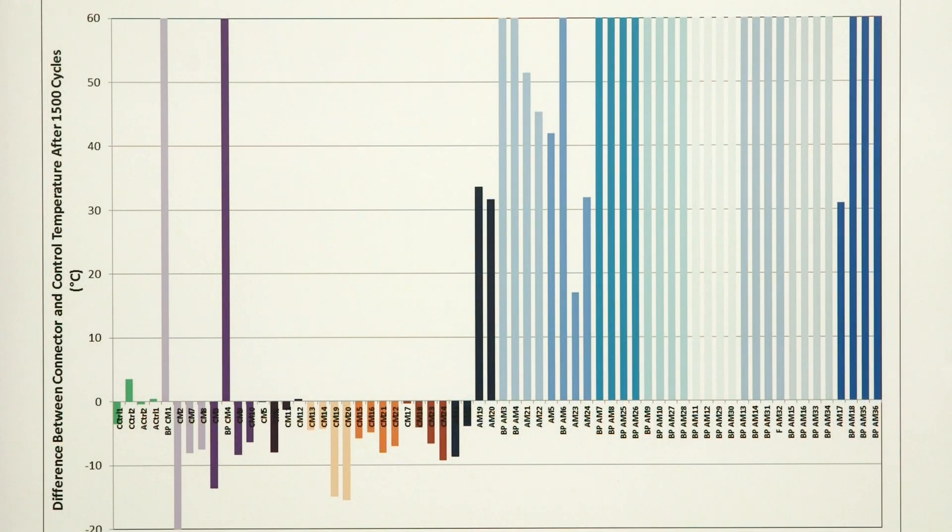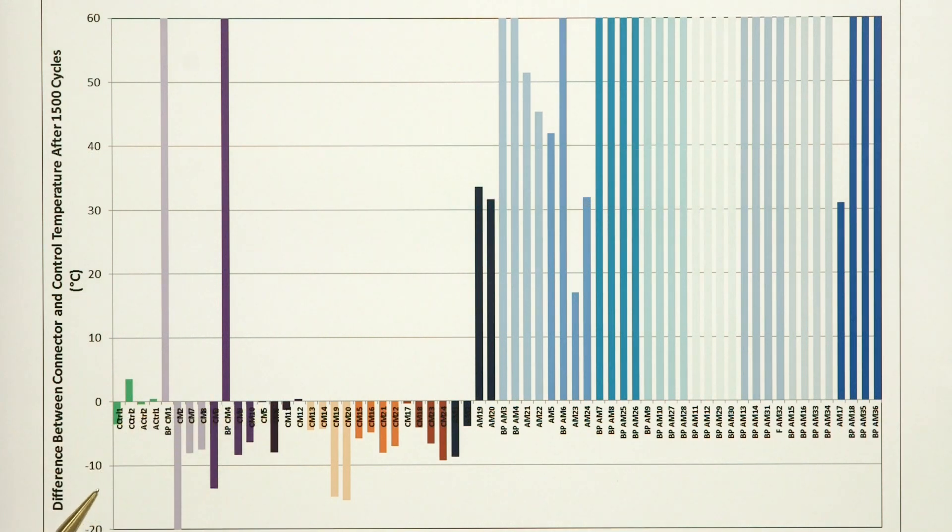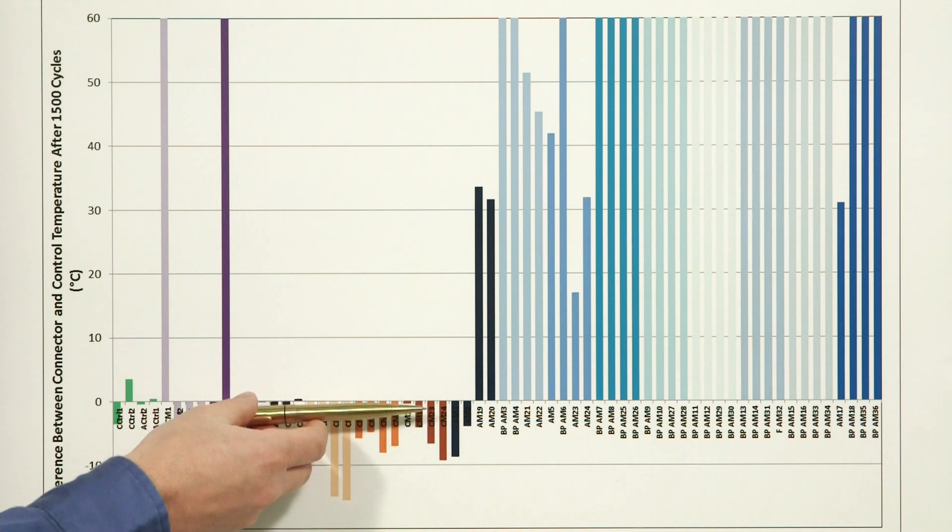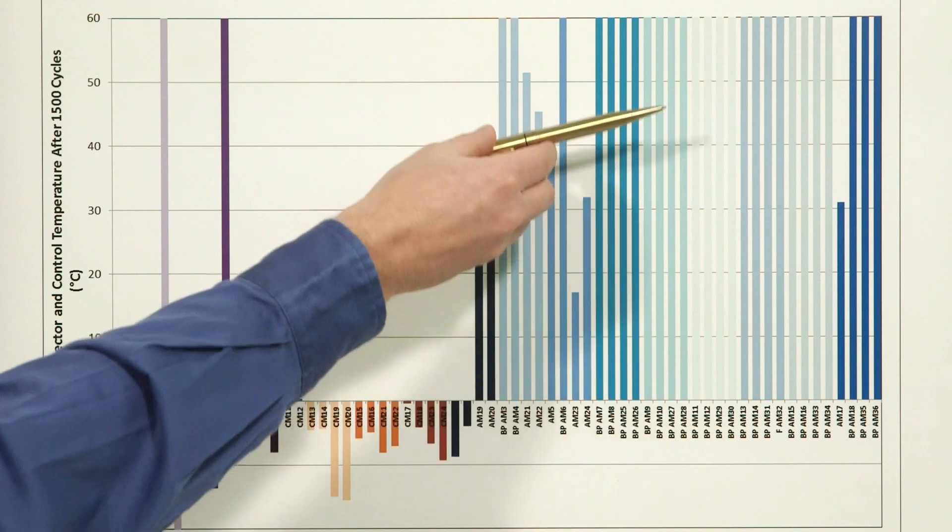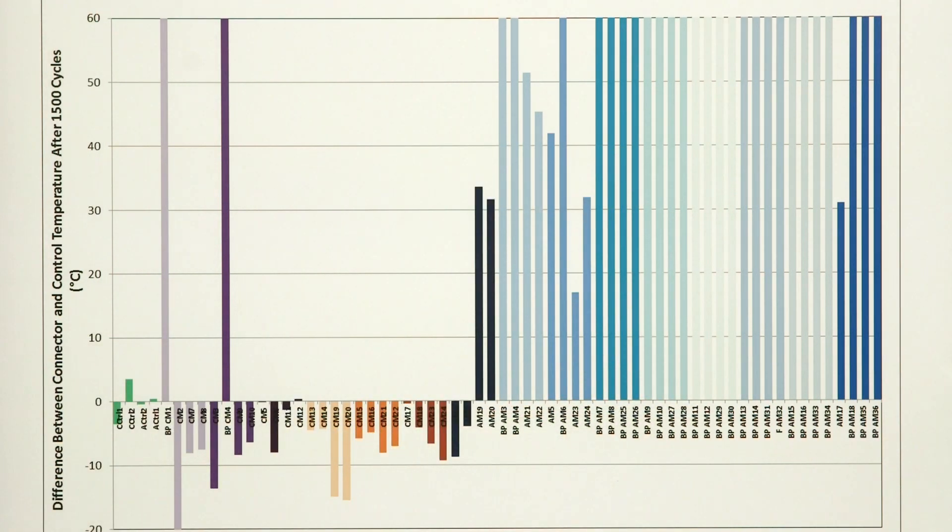Here we see in this chart again we have the temperature difference between the sample temperature and the control, except in this case this is the final value after the 1500 cycle test is complete. So here we see the majority of the samples that had copper wire with dual rated aluminum connectors are below the zero line, and all of the samples of the copper wire with copper connectors are below the zero line. And the majority of the samples that had aluminum wire with aluminum connectors are well above the line.